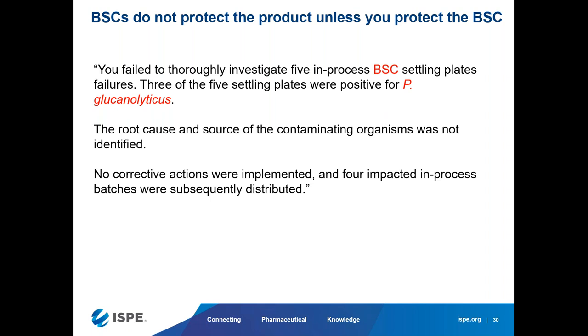Very true. You failed to thoroughly investigate 5 in-process BSC settling plate failures. 3 of the 5 settling plates were positive with Paenibacillus glucanolyticus. The root cause and source of the contaminating organisms was not identified. No corrective actions were implemented, and 4 impacted in-process batches were subsequently distributed.